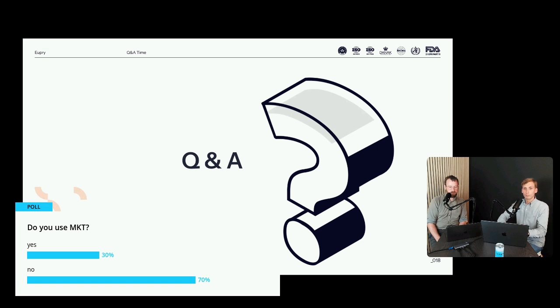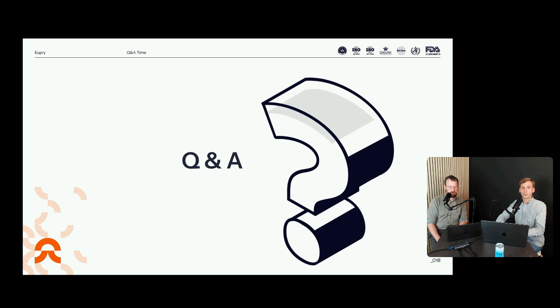So there's a question here. Is there a requirement for 1, 2, or 3 point calibration of your testing devices before performing your mapping exercise? I can't actually remember whether it's a requirement, but metrologically, it only makes sense. Yes, okay, now I remember, the WHO guidelines do require a 3 point calibration, and that is due to the metrological calibration of the devices. The measurement error of any temperature device will almost always be a second degree polynomial, so it'll be a curve like this. And the only way to define that curve is with 3 points. So there is a technical reason behind why one would need a 3 point calibration, and it only does make sense.